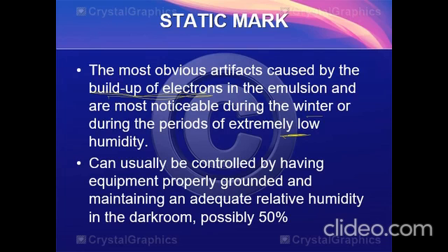So, ibig sabihin, pag ang humidity inside the dark room is below or less than 40%, it will lead to the production of static marks. So, kailangan between 40 to 60% ang humidity inside the dark room para walang static marks.